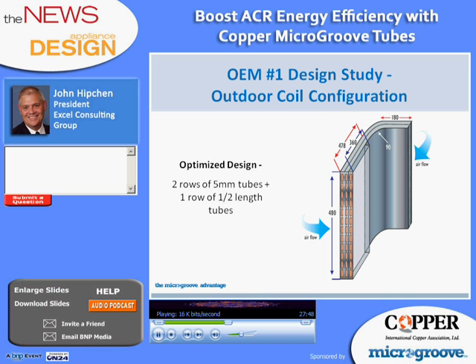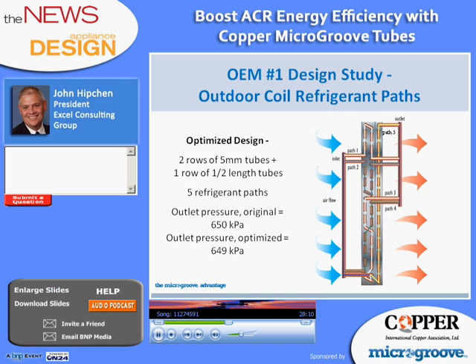This slide depicts the optimized coil for the outdoor unit. And you can now see what they meant by a half-length row of tubes. This design maintains the original concept, but it uses considerably smaller diameter tubes than the original design. And again, when we look at the 5 paths that the refrigerant can take in the optimized design, and compare it to the 2 paths in the original, we can understand how the pressure drop is managed with the much smaller 5 millimeter tubes. The multiple paths offer much less tubing to flow through, and therefore a minimal amount of pressure is lost in the process. And be sure to note the nearly identical pressure drop measured in the original versus the optimized coil. Also, the inlet and outlet now show the refrigerant flowing the same direction as the air.